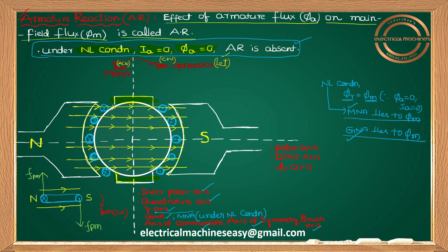This point is very important. But don't think that under load condition also GNA and MNA will be coinciding. No. Because under load condition, phi a is not equal to 0. So your phi r is not equal to phi m. Your phi r is different. So your MNA will shift from GNA by some angle theta, that we'll discuss anyway.